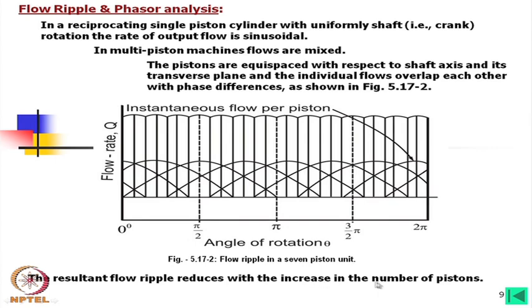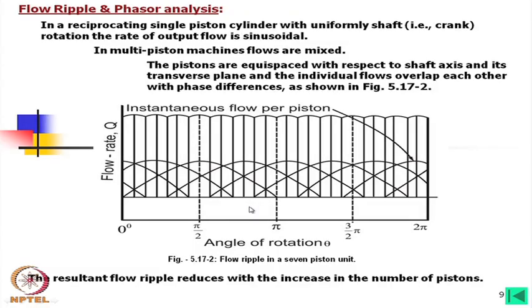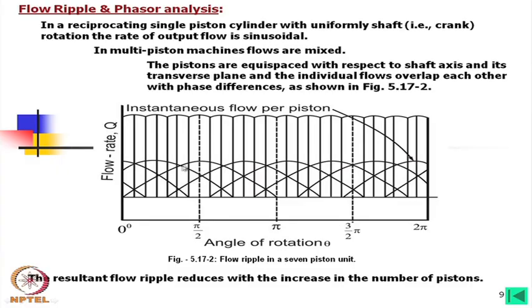The resultant flow ripple reduces with increasing number of pistons. For a single piston, delivery occurs only in half the cycle. When multiple pistons are mixed, when one piston is in suction mode, other pistons are in compression mode and delivering oil. So the ultimate flow ripple is a fluctuating curve — and with increasing number of pistons, that fluctuation decreases.